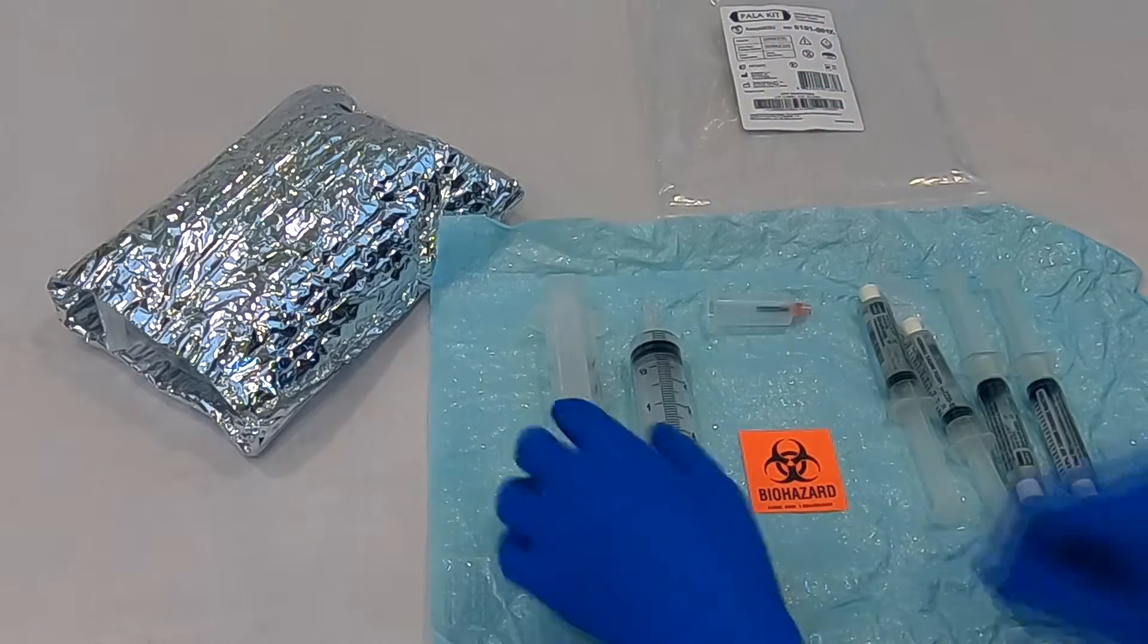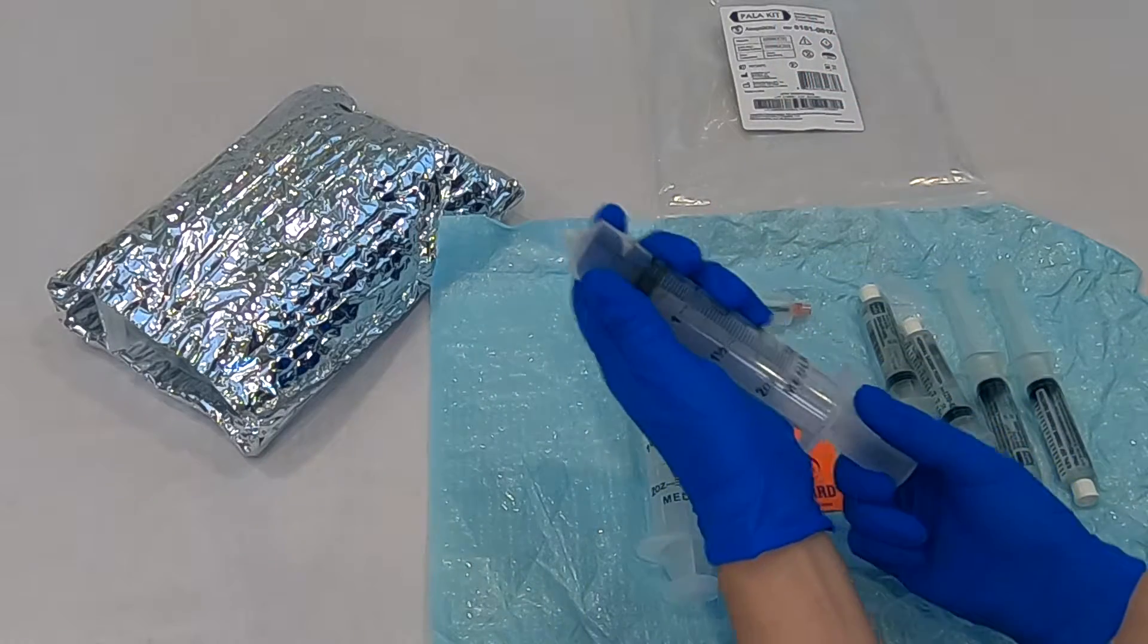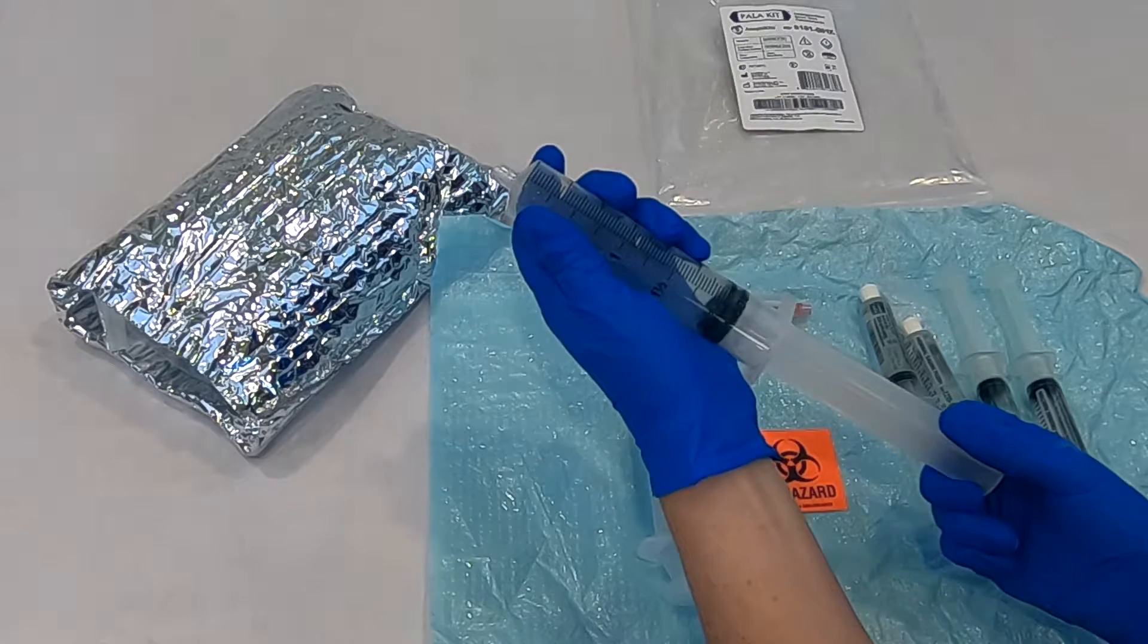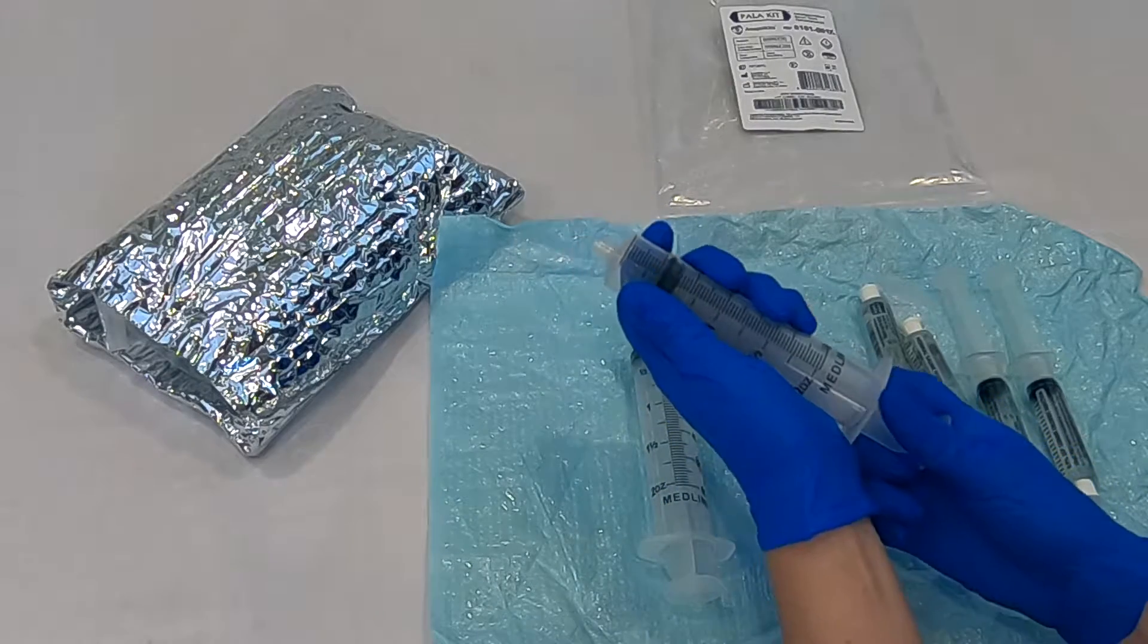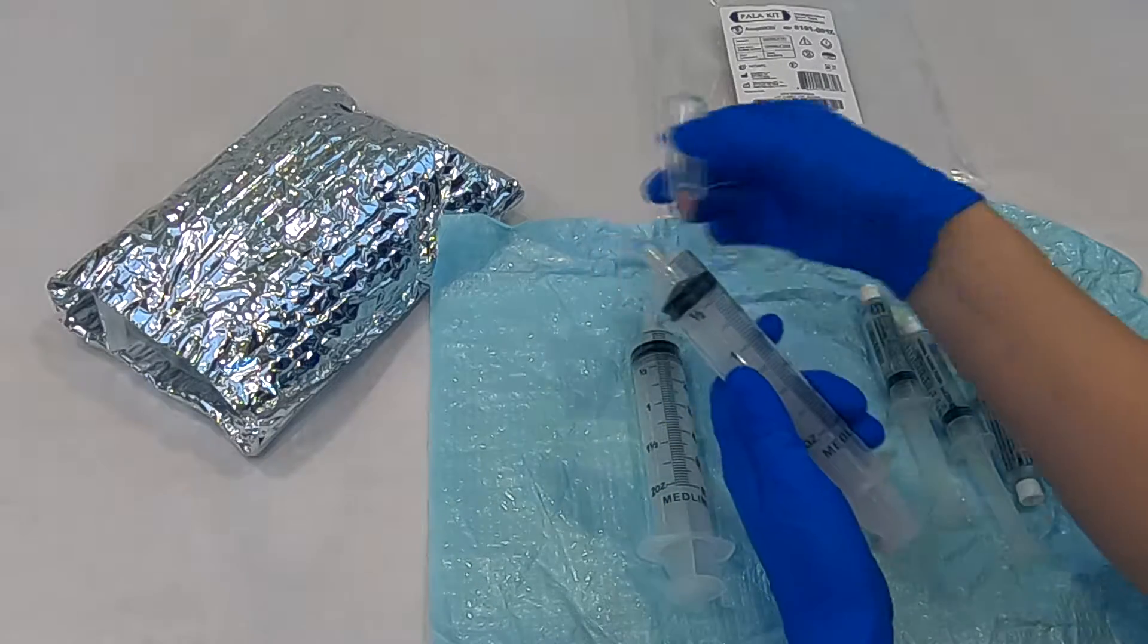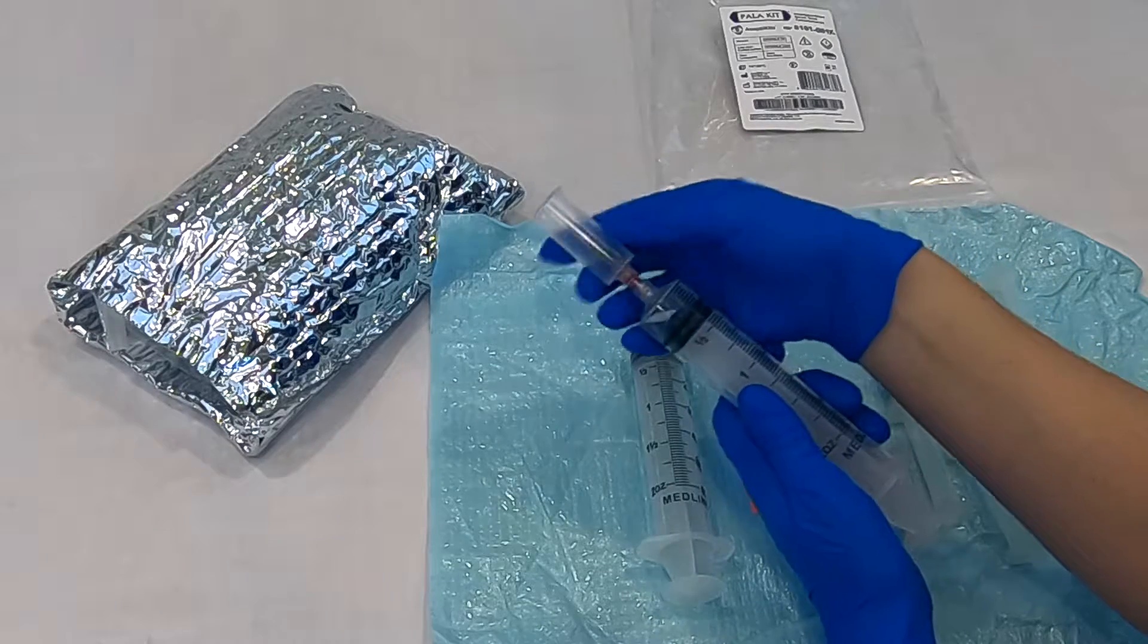For this first step, access the 60 milliliter syringe without the female-to-female luer adapter. Break stiction for ease of use. Connect the phlebotomy fluid transfer barrel to the conventional syringe.